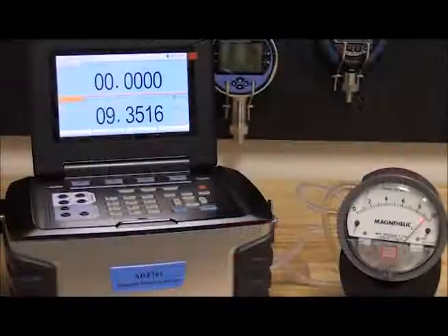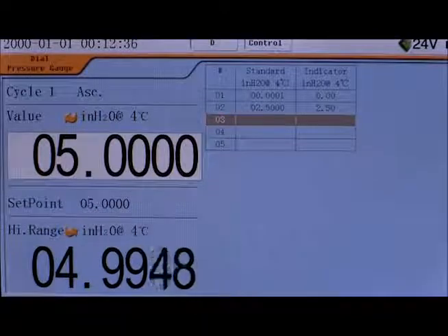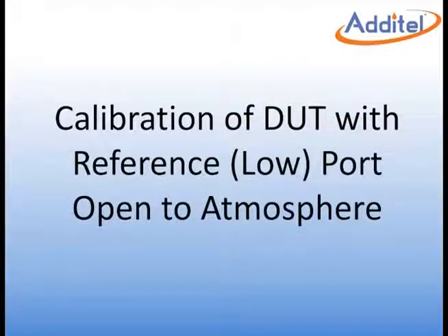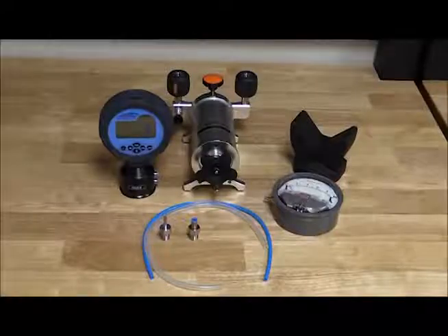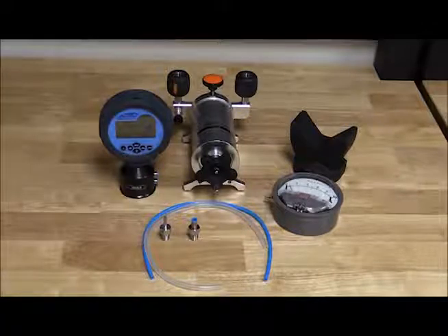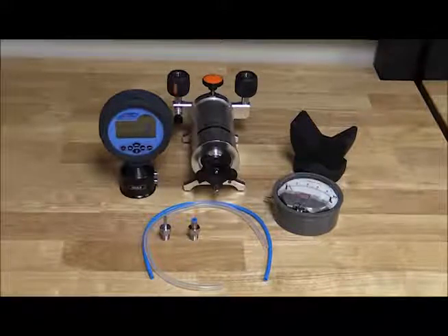In this video we will demonstrate three different ways to calibrate a differential pressure gauge and the pros and cons of each method. We will use an Additel 901 pump to generate the pressure. The Additel 681 differential gauge will be used as our accurate reference, and we will be calibrating a Magnehelic differential gauge that is 0 to 10 inches of water.